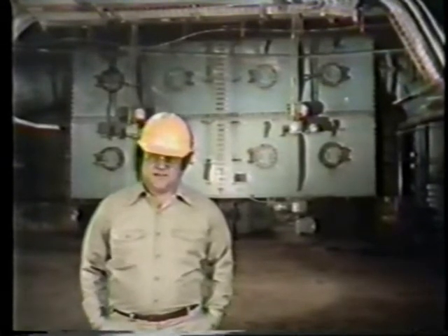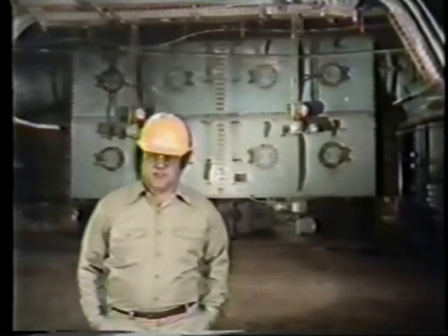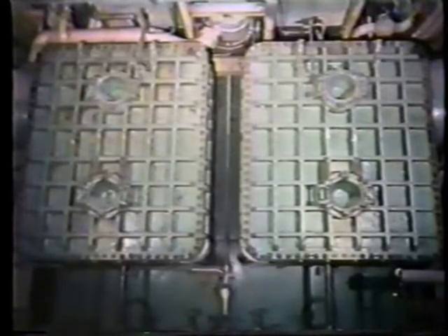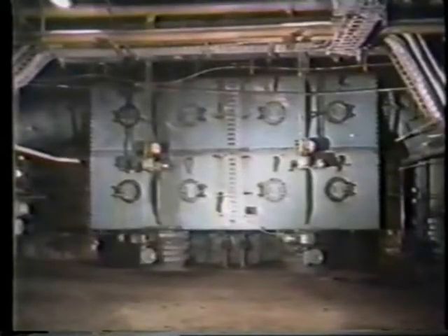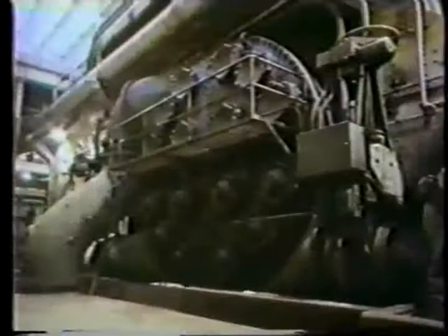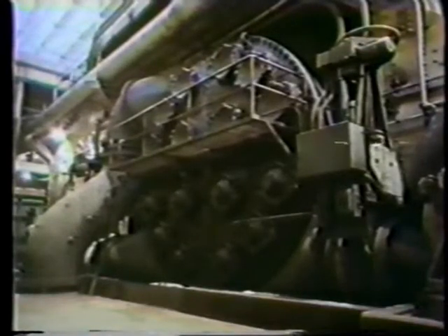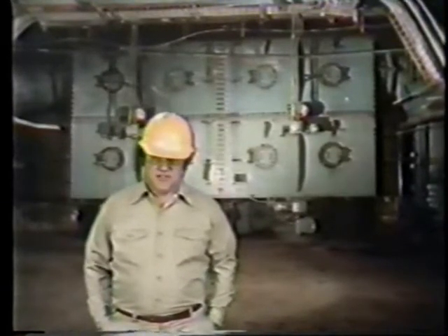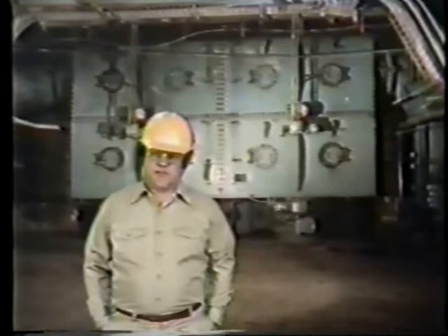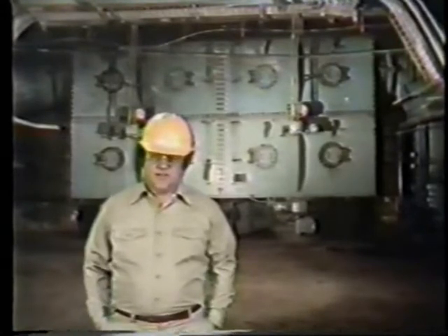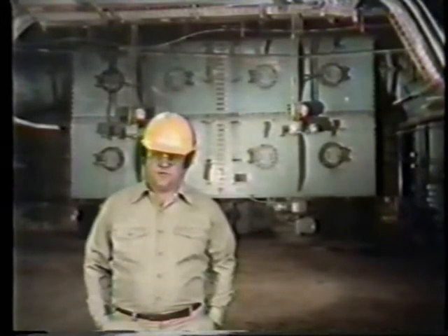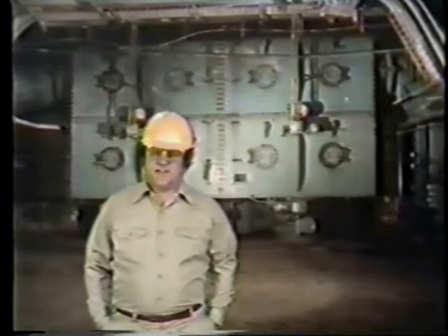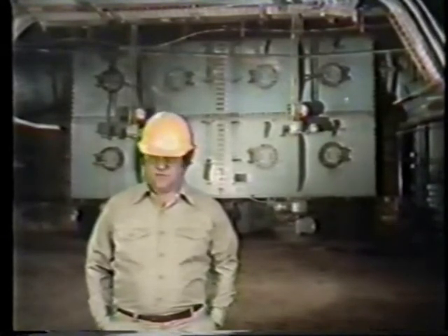We'll begin with main condensers, their function, construction, and operation. Regardless of the design or type of condensers used in a plant, their main function is to convert the steam exhausted from turbines into condensate. The condensation process improves a plant's efficiency. Most main condensers operate at pressure less than atmospheric. This vacuum increases the overall pressure drop across the turbine and increases the useful power output of the turbine.